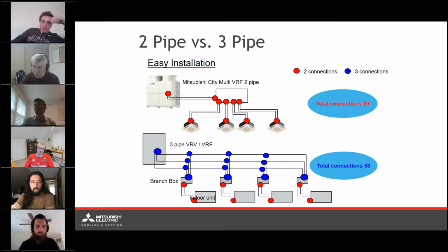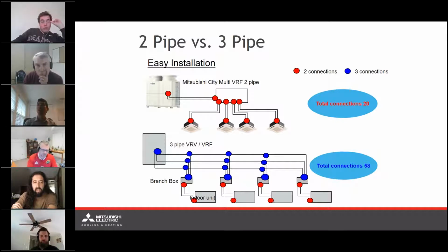All right. As a demonstration, this is a slide we often see that differentiates Mitsubishi or any two-pipe heat recovery manufacturer from three-pipe heat recovery manufacturers. I'm not using this time to say one way or the other whether two-pipe is better or three-pipe is better. Me personally, I've worked for manufacturers that did both. So there are certainly advantages to both methods, but ultimately I'm trying to draw the corollary between the two-pipe City Multi Mitsubishi VRF and HVRF, and how we're ultimately reducing those refrigerants.